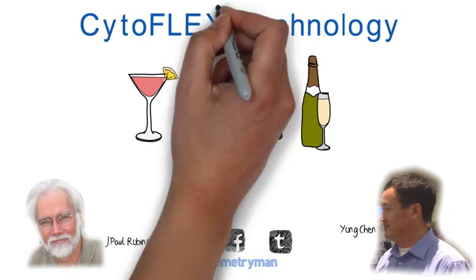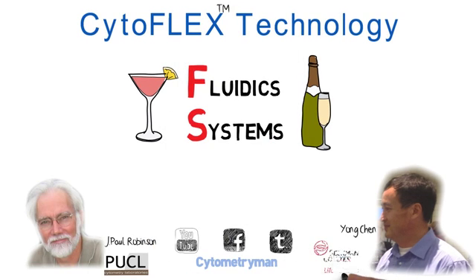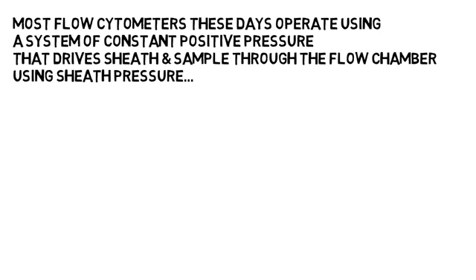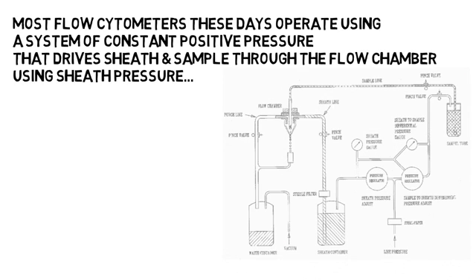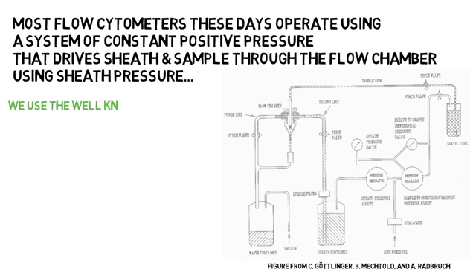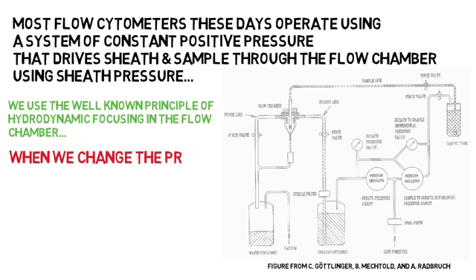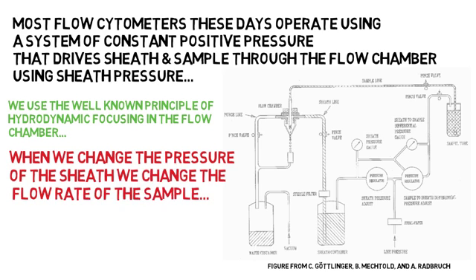In this tutorial, we're going to talk about fluidic systems and understand the differences between the Cytoflex and other instruments. Most flow cytometers these days operate using a system of constant positive pressure that drives the sheath and sample fluid through the flow chamber, using the well-known principle of hydrodynamic focusing. When we change the pressure of the sheath, we change the flow rate of the sample.